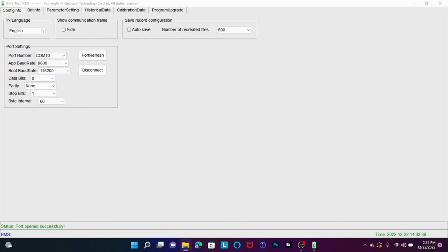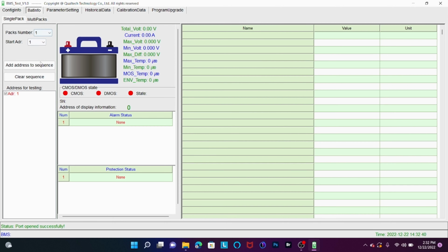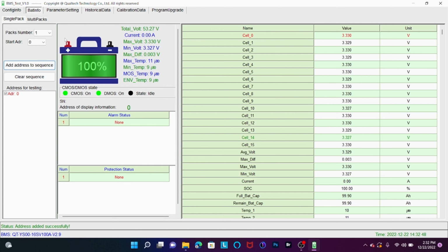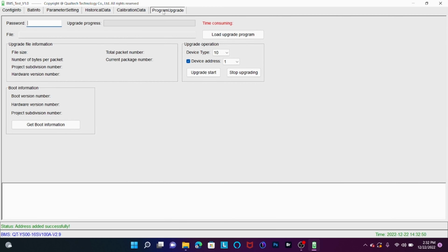With our COM port already set correctly, we're going to go to Battery Info. We're going to clear the sequence, change the starting address to 0, and add the address back to the sequence. Now our battery is communicating with our laptop. Let's go to Program Upgrade. We're going to change our device address to 0. We're going to click Get Boot Information so we know which hardware version we have. So our battery has 0205.